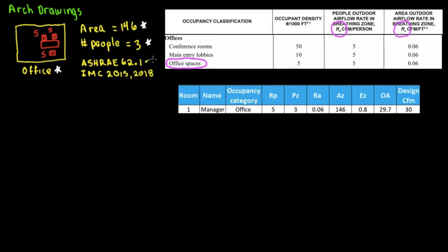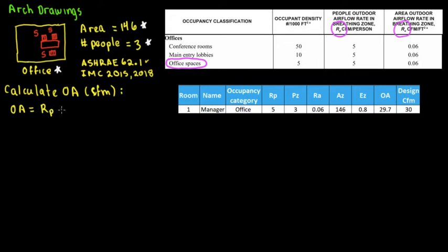So based on ASHRAE 62.1, what is the formula? We need to calculate the CFM — cubic feet per minute — of outside air. The ASHRAE 62.1 formula is: Outside Air = (RP · PZ + RA · AZ) / EZ. That's the formula. Outside air is going to be equal to that.